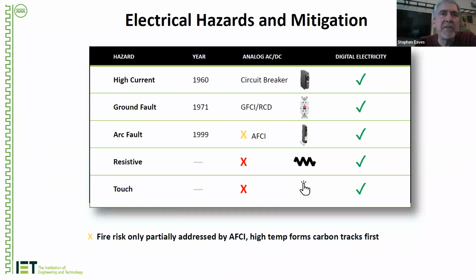Finally, another important aspect of safety detection that's not addressed in conventional technologies is touch fault. So if you have a cord, like say you're using an insulated device like a vacuum cleaner that has a plastic shell, there's really just two wires in the cord. There is no ground wire coming back from a double insulated device. If you strip back the insulation on that power cord, you'll expose the power conductors. In the US, there's a hot and a common, as we call it. And if you touch those two wires, then you'll be shocked.